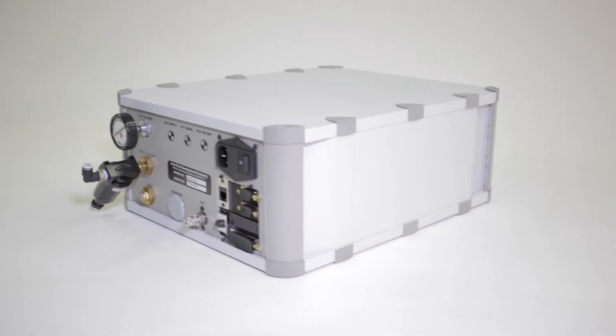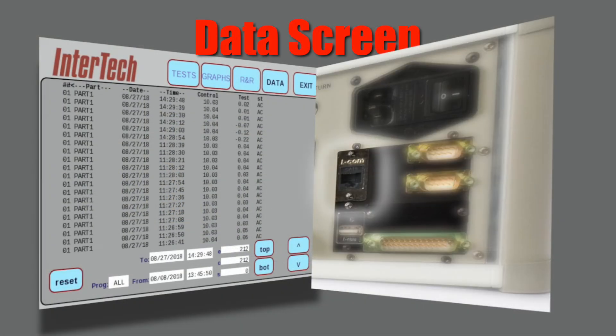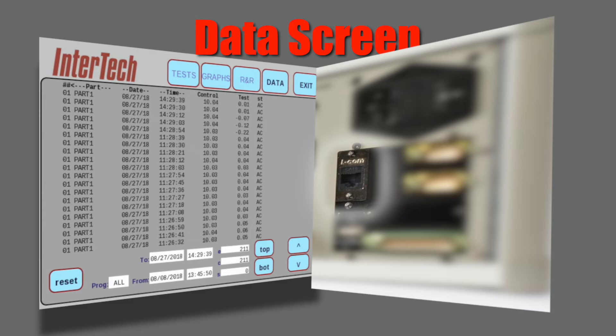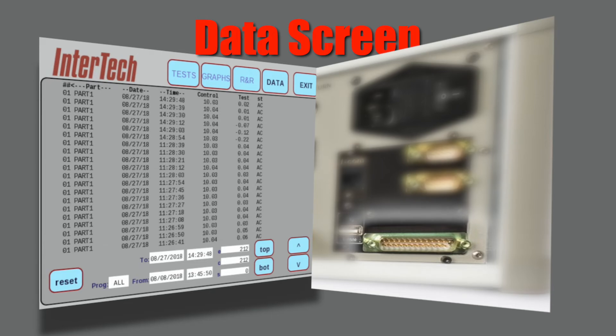Data can also be offloaded to an acquisition system using the RS-232 port or Ethernet port. The M1075 also includes an embedded web page for remote test cycle viewing. The Ethernet port can be used for Ethernet IP or PROFINET system control interface. The printer port connections are used for user I/O interface where Ethernet IP is not used.